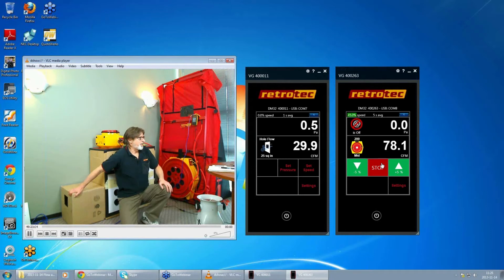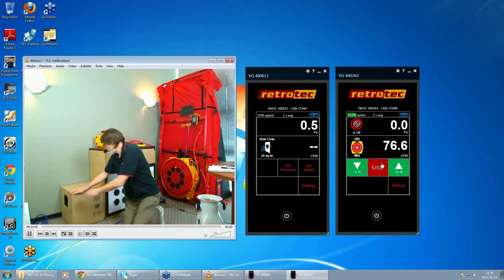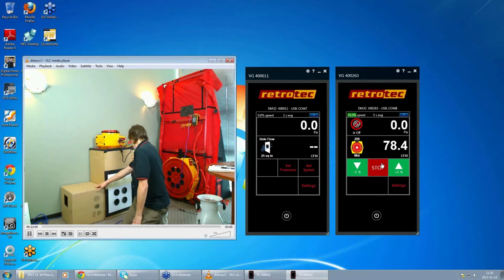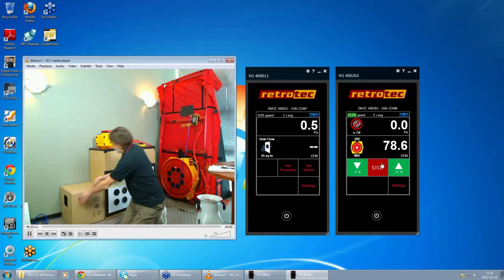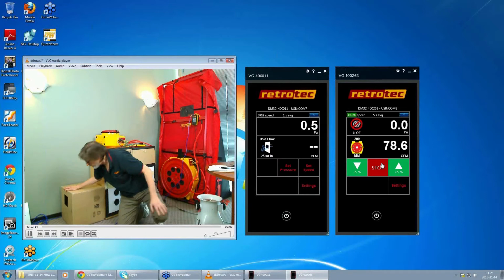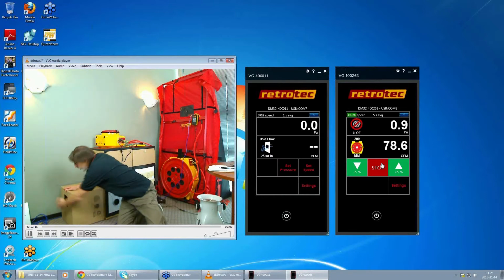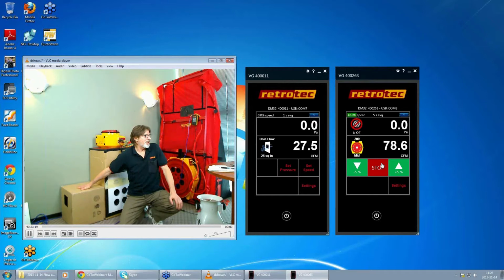So you noticed before in the depressurization mode, we got pretty good results, but pressurizing this box, we're not getting anywhere near the kind of results that we got before. You'll notice that the results are bouncing around all over the place, and this indicates the problem we have of measuring supply flows versus exhaust flows. So supply flows are really tough to measure. You notice that we're kind of going in and out and all over the place here.